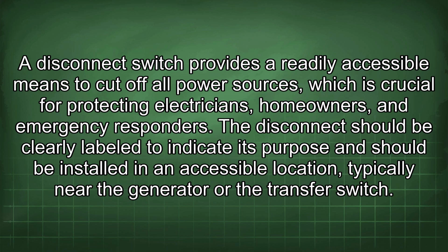A disconnect switch provides a readily accessible means to cut off all power sources, which is crucial for protecting electricians, homeowners, and emergency responders. The disconnect should be clearly labeled to indicate its purpose and should be installed in an accessible location, typically near the generator or the transfer switch.